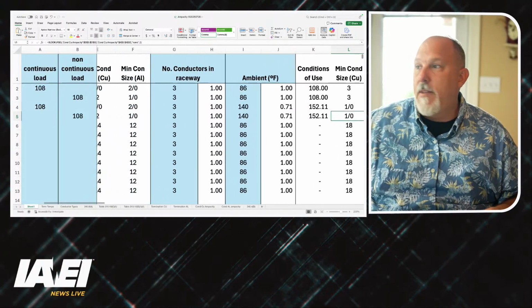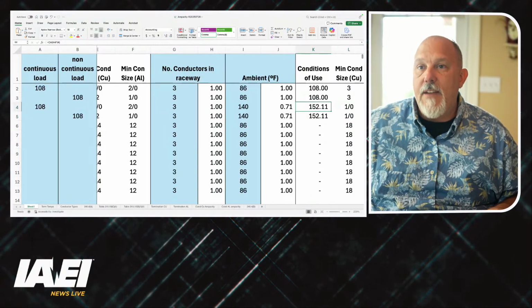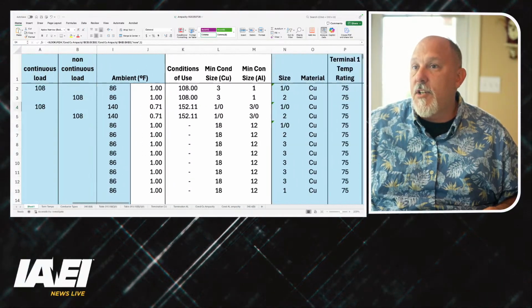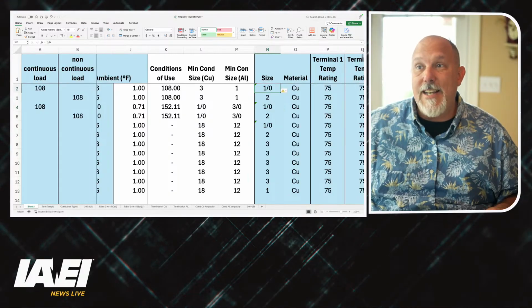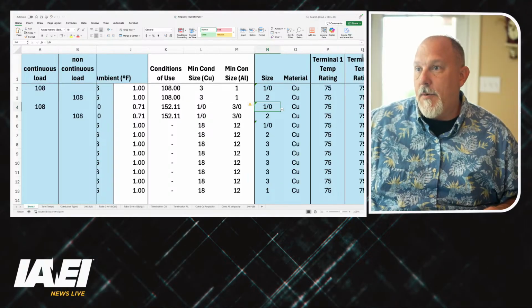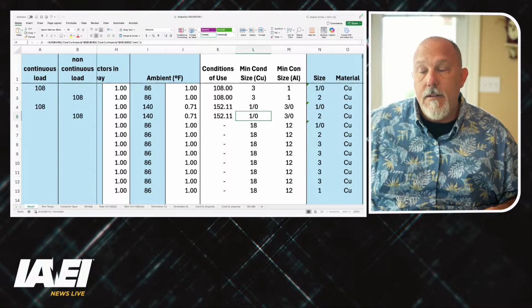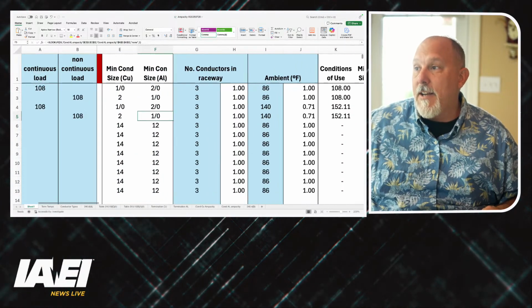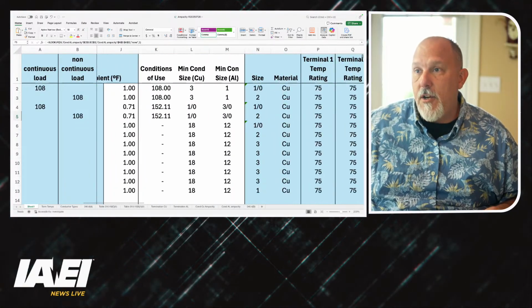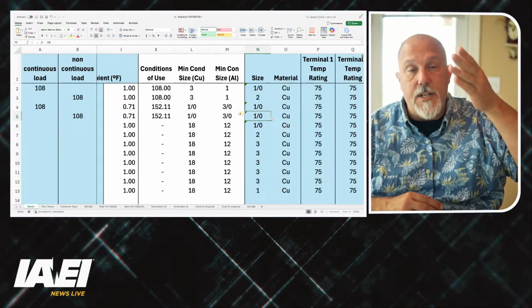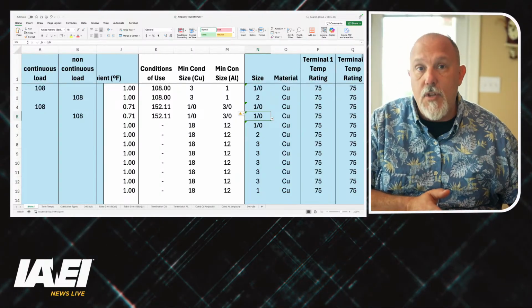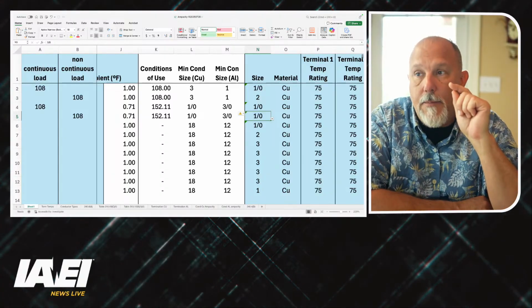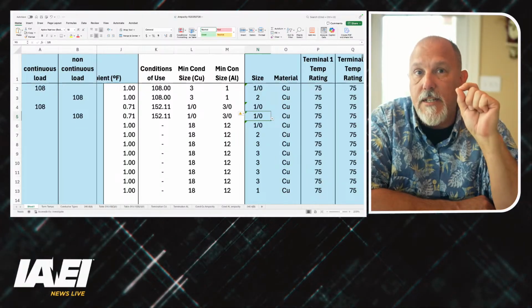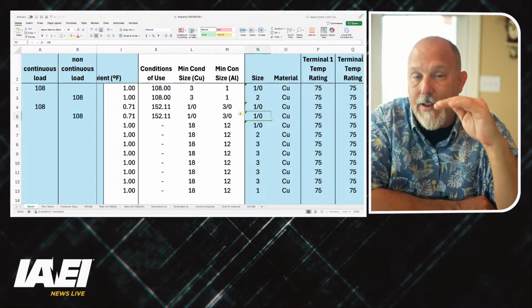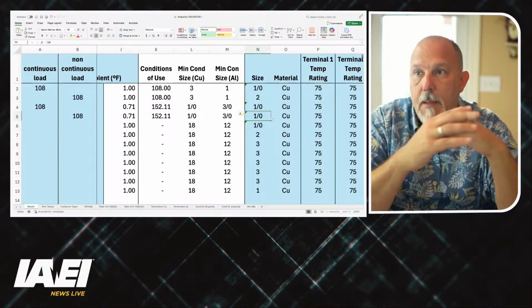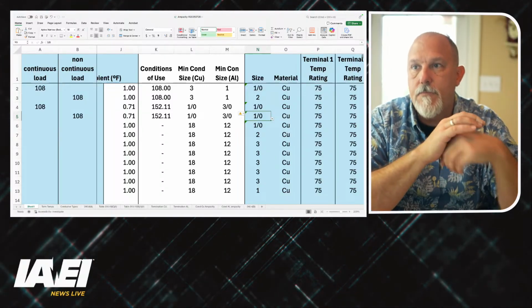So the larger of the 2, let's start with 108 amps of continuous. I have a 1 aught conductor and I have a 1 aught conductor. So I'm going to stick with a 1 aught conductor, which is exactly what I had before. For the non-continuous, I have a 1 aught conductor, and I have a 1 aught conductor for the conditions for the 125%. So in both cases, I'm into a 1 aught conductor, whether it is 108 amps of continuous load or 108 amps of non-continuous load. Regardless, I'm using the same size conductor. And hopefully you see how I got there. I did the 2 evaluations, and they both resulted in a 1 aught conductor, 1 aught copper.